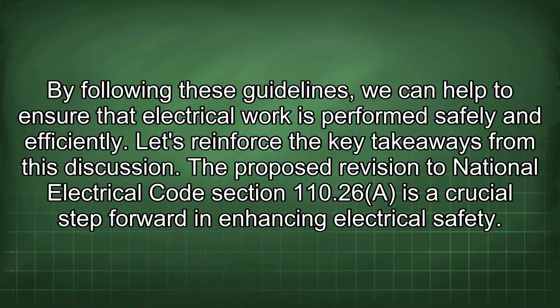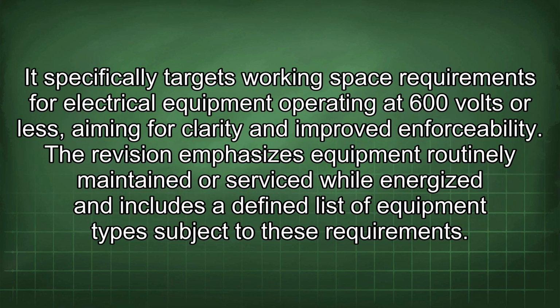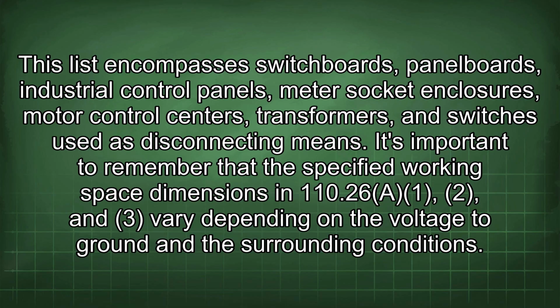Let's reinforce the key takeaways from this discussion. The proposed revision to National Electrical Code Section 110.26 is a crucial step forward in enhancing electrical safety. It specifically targets working space requirements for electrical equipment operating at 600 volts or less, aiming for clarity and improved enforceability. The revision emphasizes equipment routinely maintained or serviced while energized and includes a defined list of equipment types subject to these requirements. This list encompasses switchboards, panelboards, industrial control panels, meter socket enclosures, motor control centers, transformers, and switches used as disconnecting means.